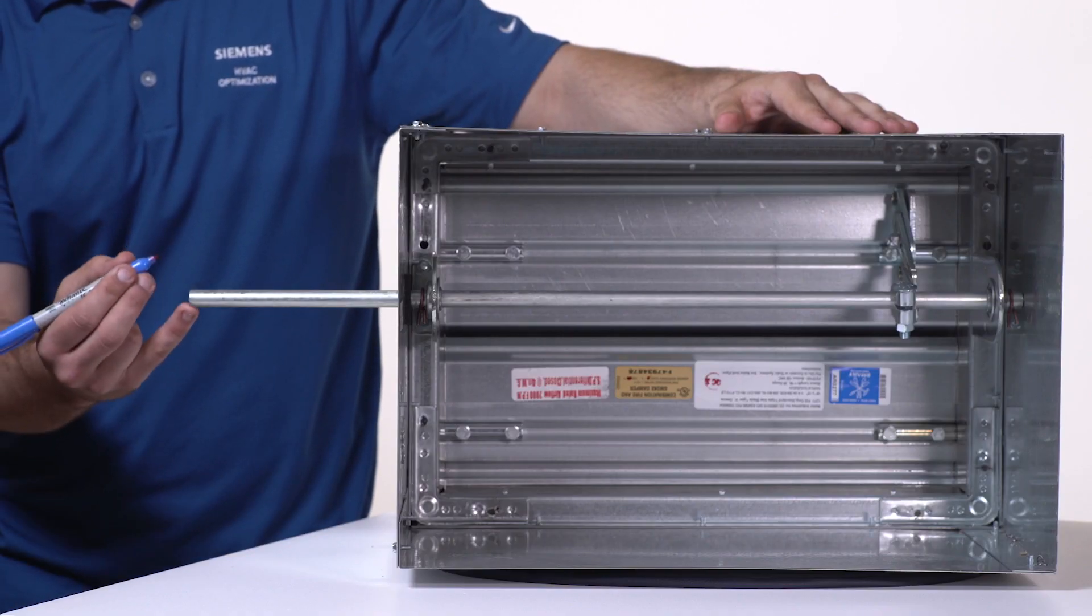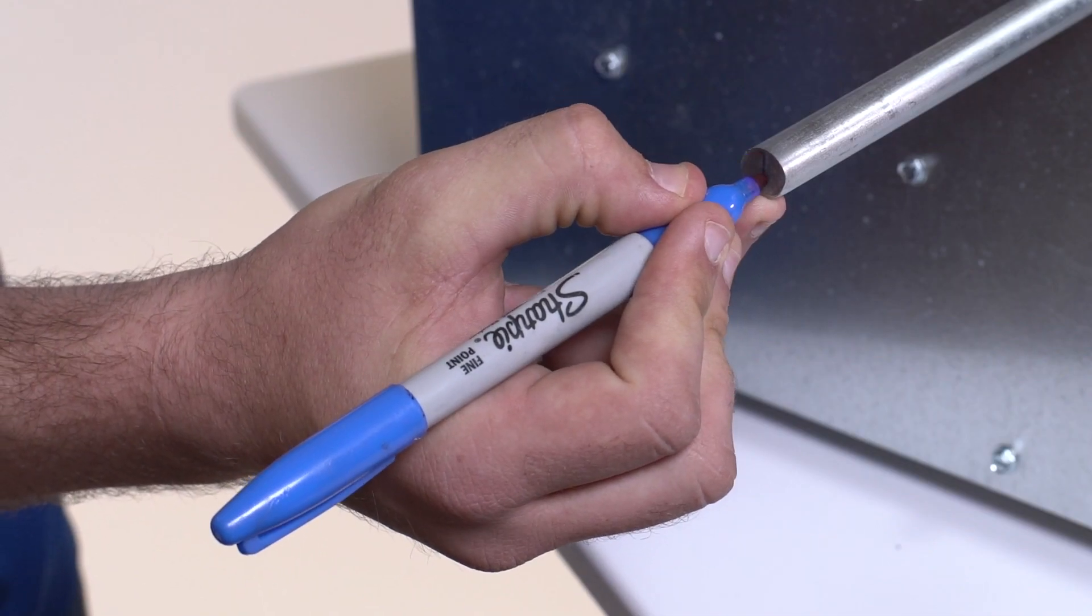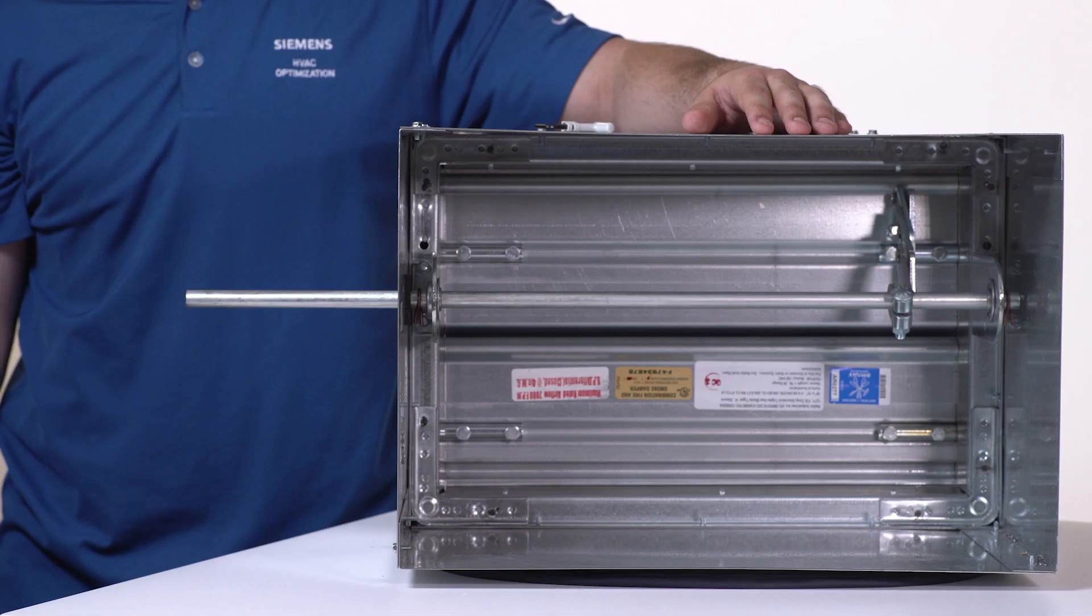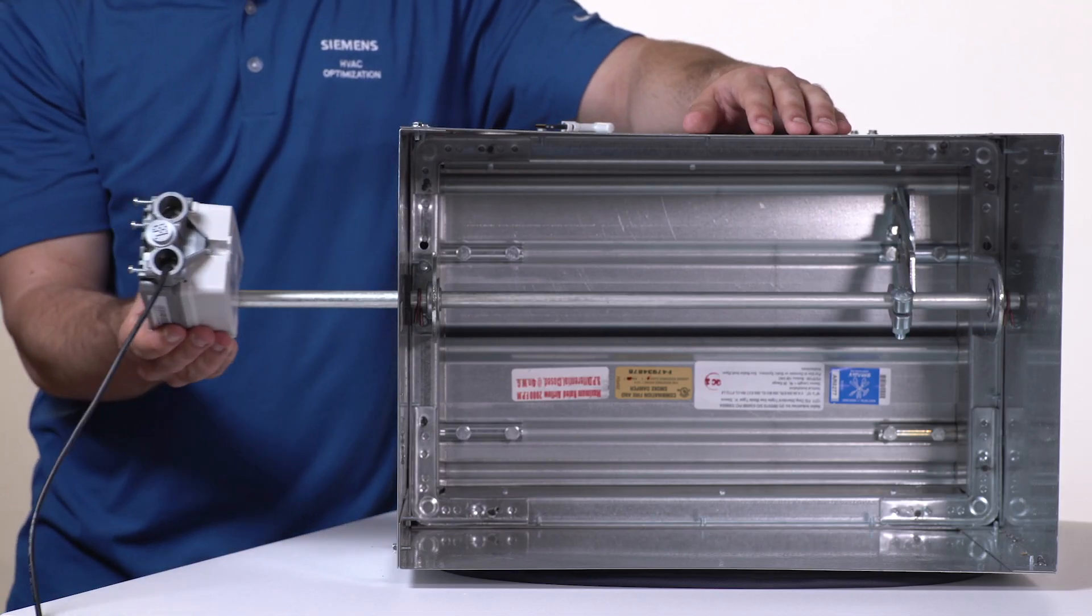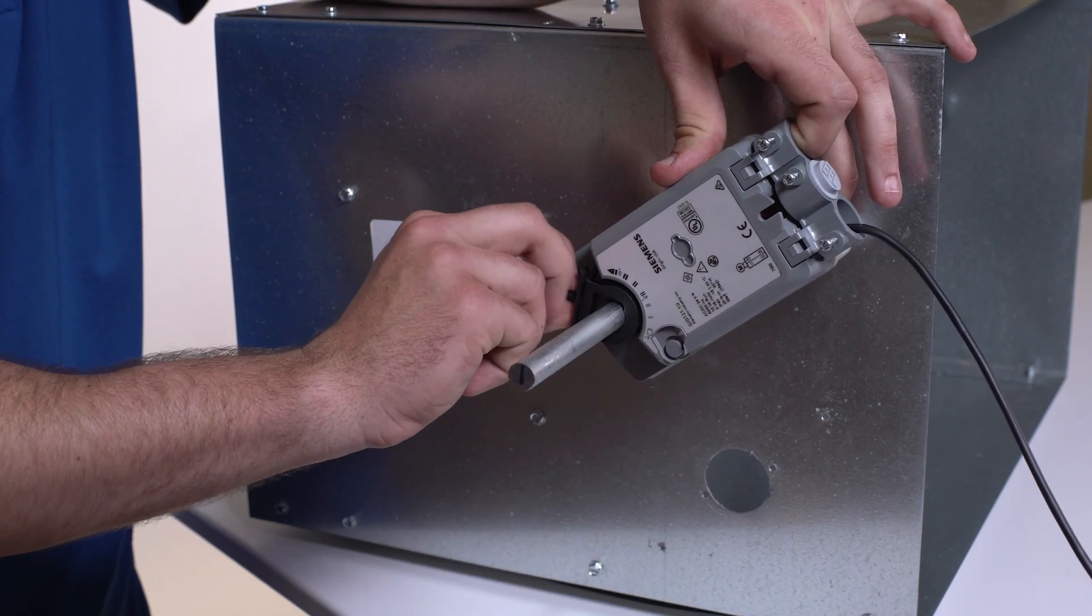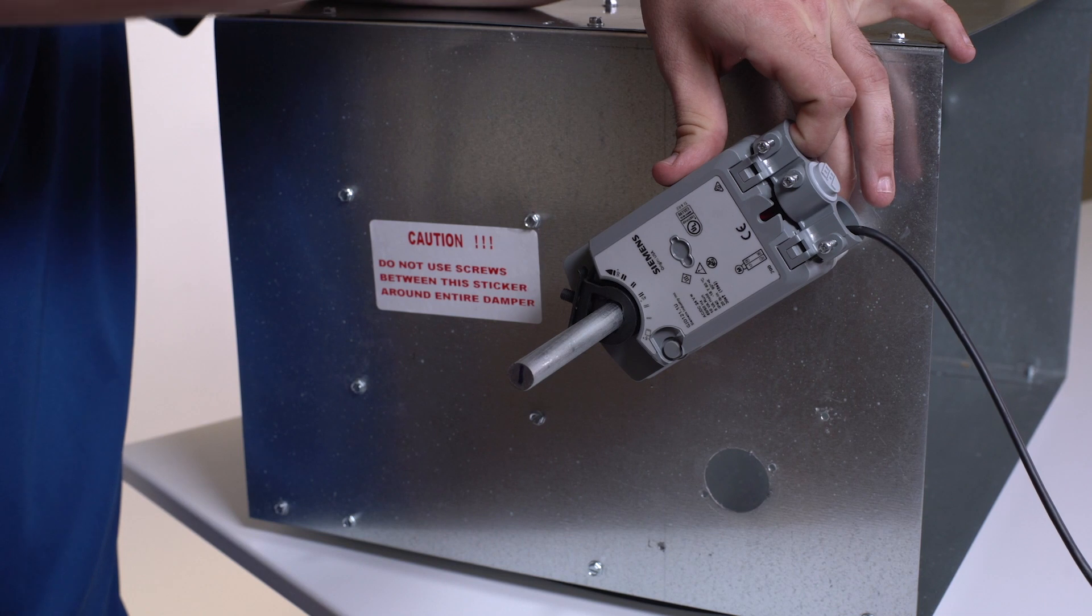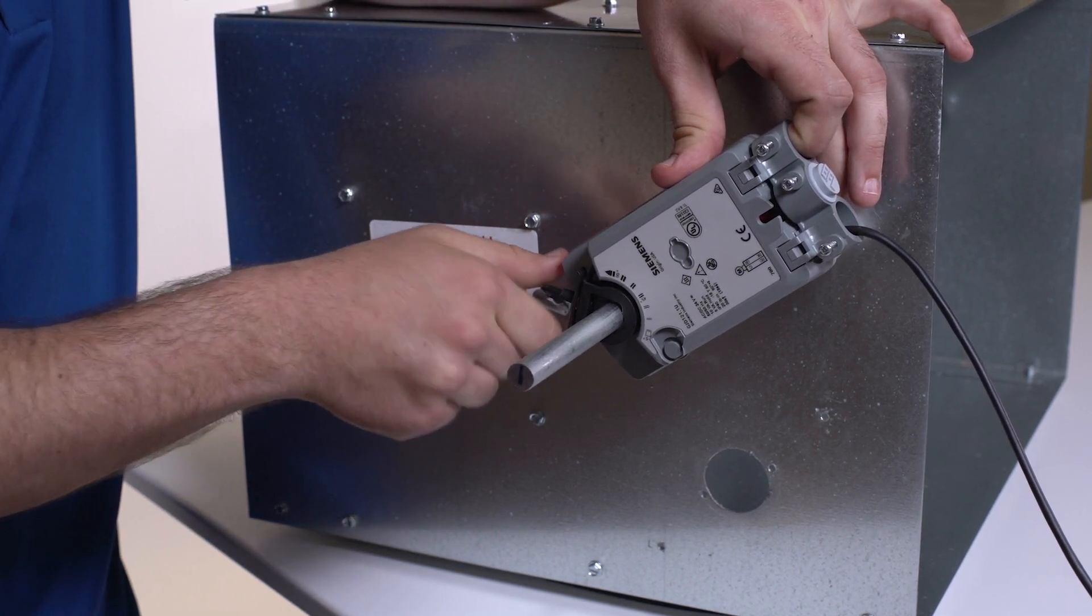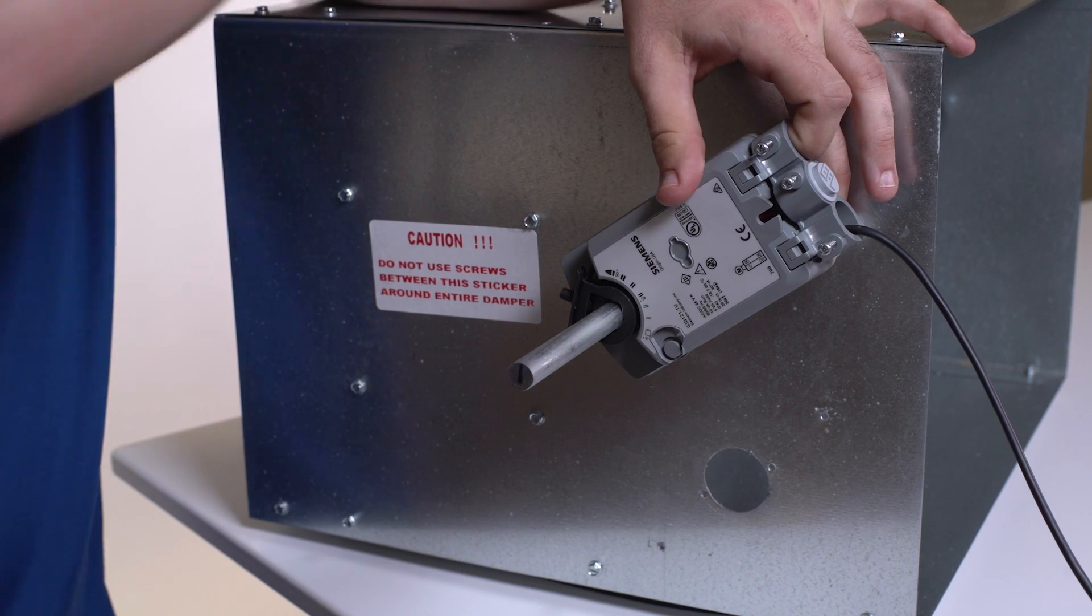Mark the shaft center line for a visual indication of the position either open or closed. Place the actuator on the shaft and tighten by hand to the specified torque. The self-centering jaws provide a secure no-slip connection and eliminate side loading.